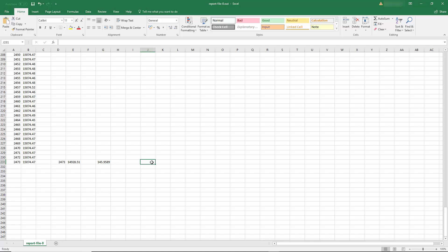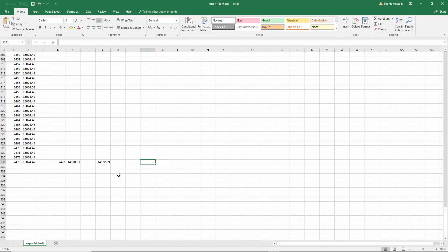To calculate the k value, we all remember, we have k is equal to the flow rate divided by the square root of delta p. The flow rate is in meter cube per hour and the delta p should be in bar.